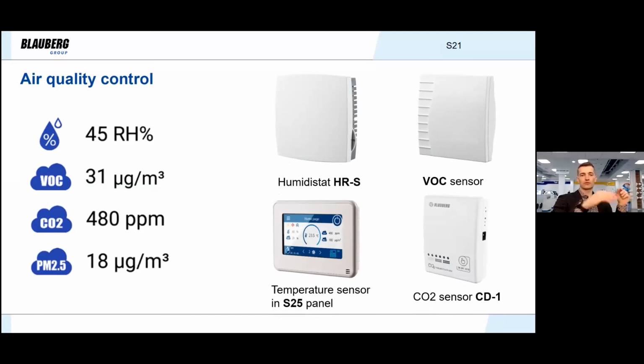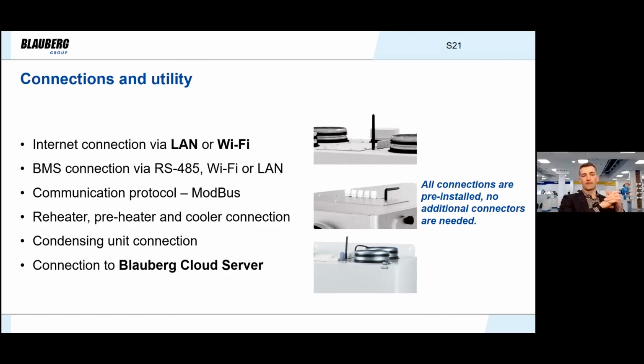And also there is a temperature sensor in the wall-mounted control panel. Some of the sensors can be installed directly inside the unit. For example, this is a humidity sensor, and other sensors can be installed on the wall and connected by wire to the unit. Let's talk about connectivity. You can connect the unit to the building management system using the type of communication that is most comfortable for you in your project. This can be either RS485, Wi-Fi or Ethernet cable. We have developed Modbus protocol. It is built into our controller, so it would be easy to connect with Modbus TCP.